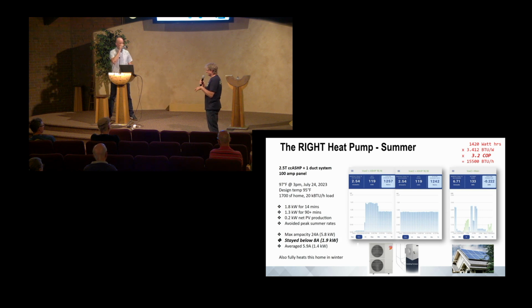A friend of mine has electric strip heaters as backup, but the software called them into action if he asked for more than a 5-degree temperature difference, or if the temperature went below 32 degrees—both completely stupid parameters. Unless you have an installer who points that out and changes those settings, you could be pretty disappointed by your electric bill, because this resistance heater is basically a toaster, and it'll cost you.